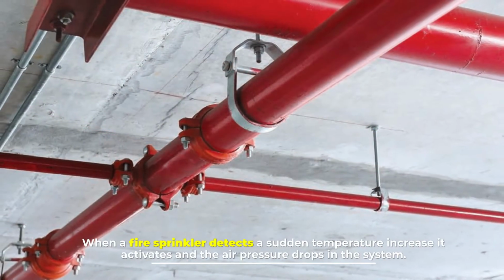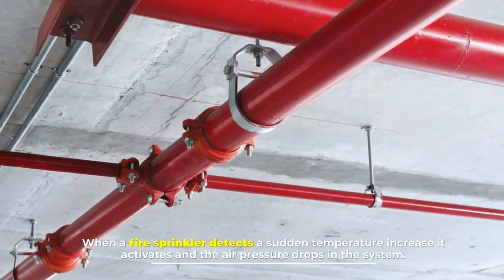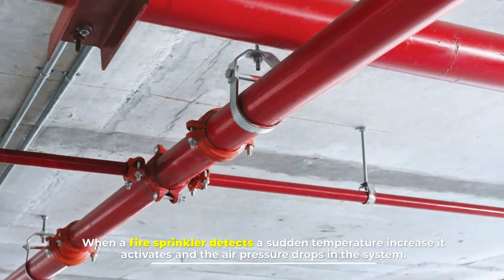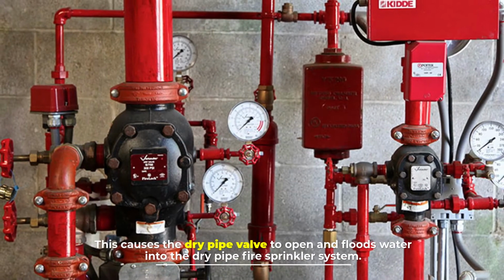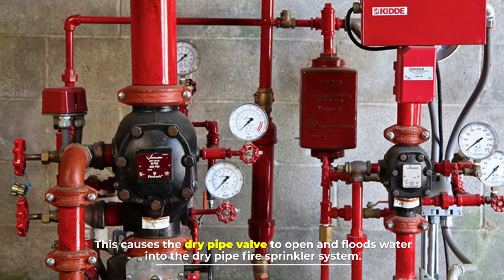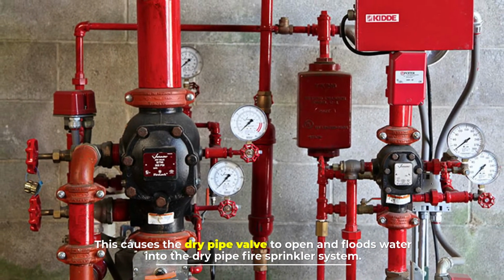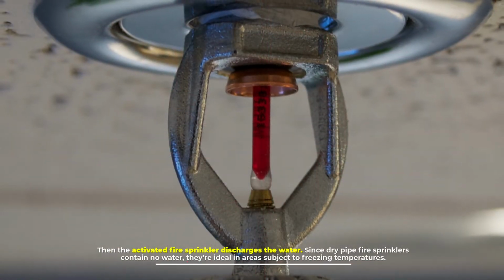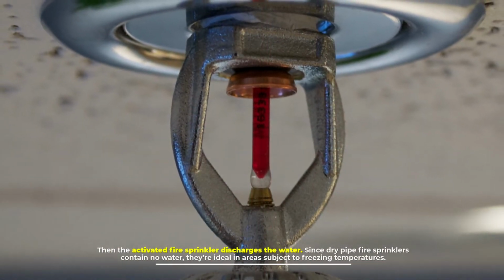When a fire sprinkler detects a sudden temperature increase, it activates and the air pressure drops in the system. This causes the dry pipe valve to open and floods water into the dry pipe fire sprinkler system. Then the activated fire sprinkler discharges the water.